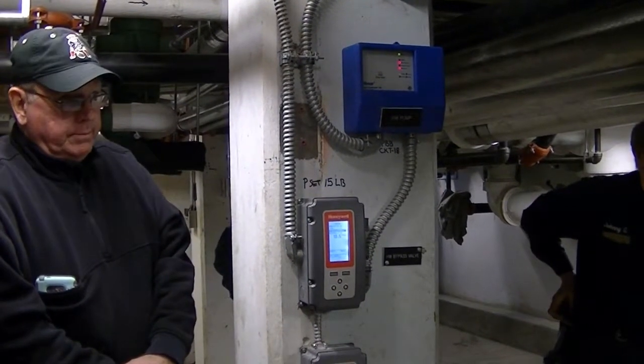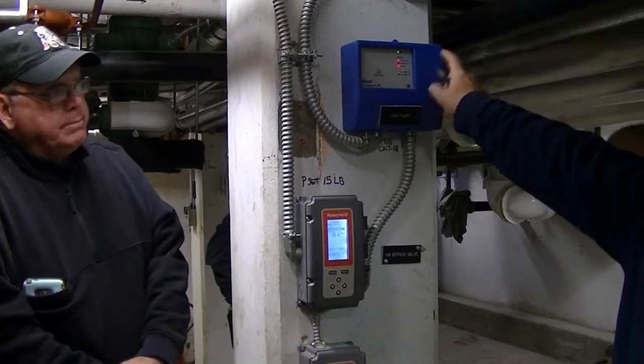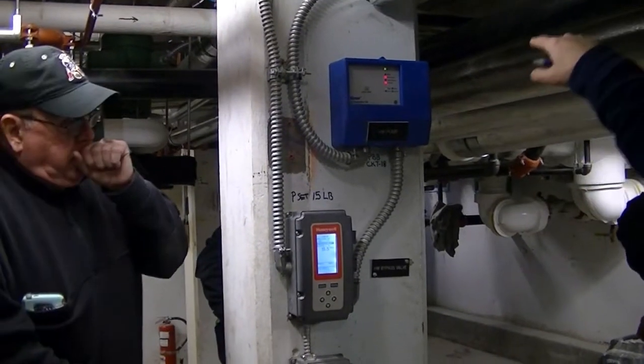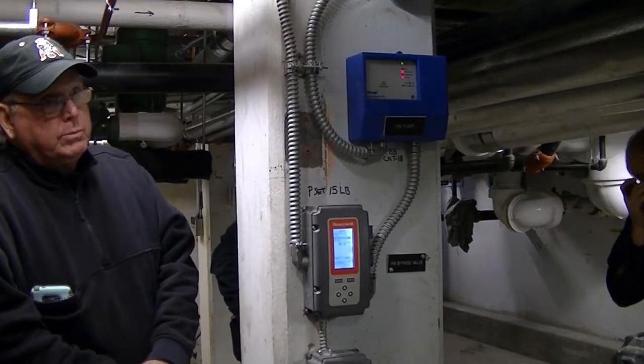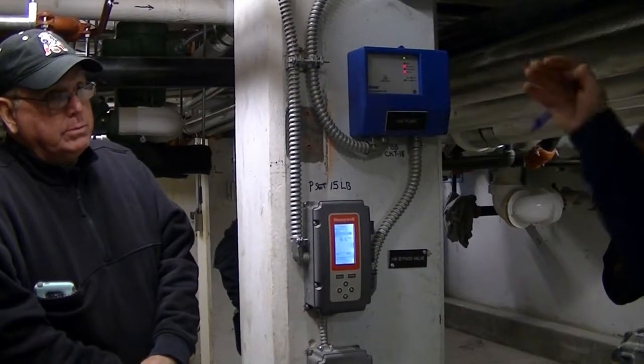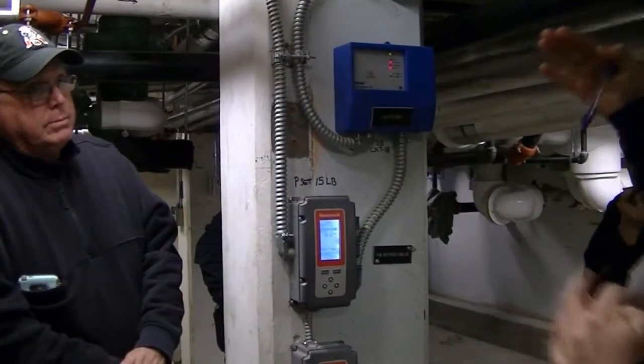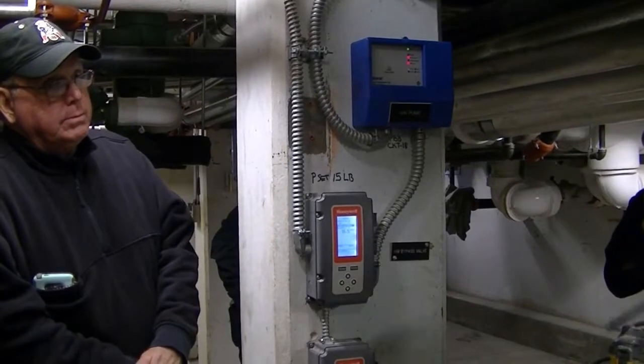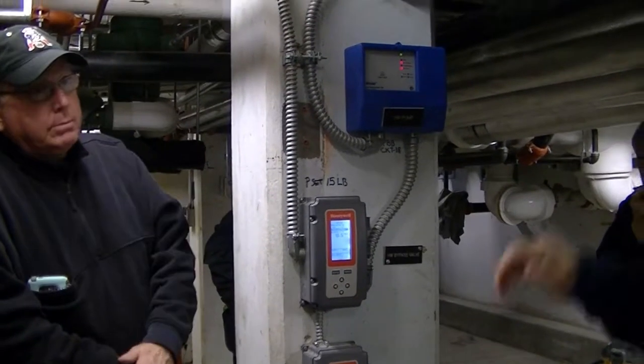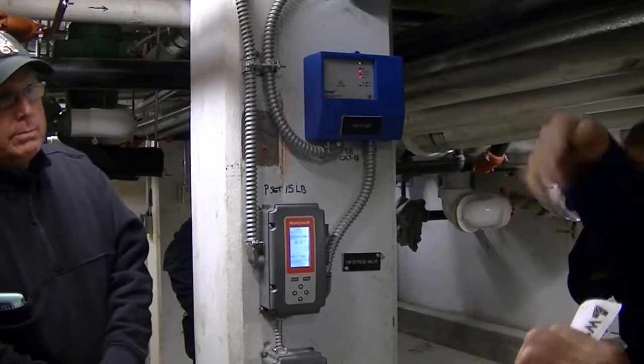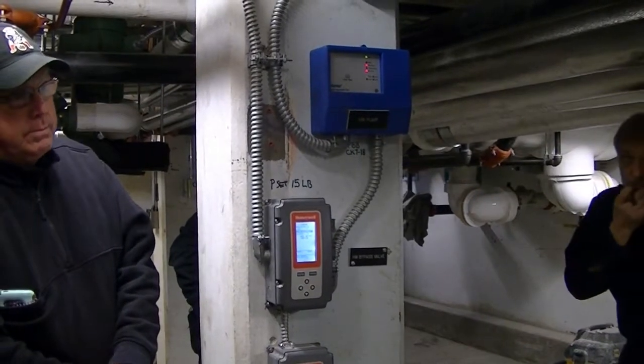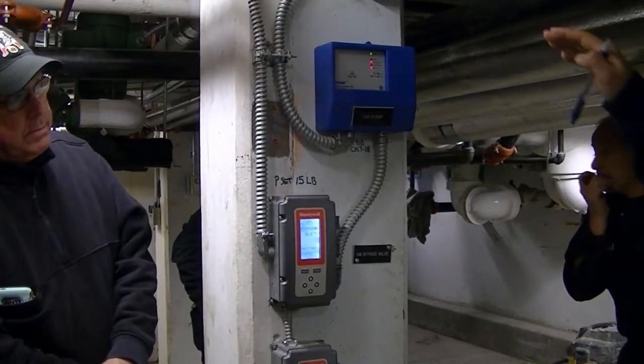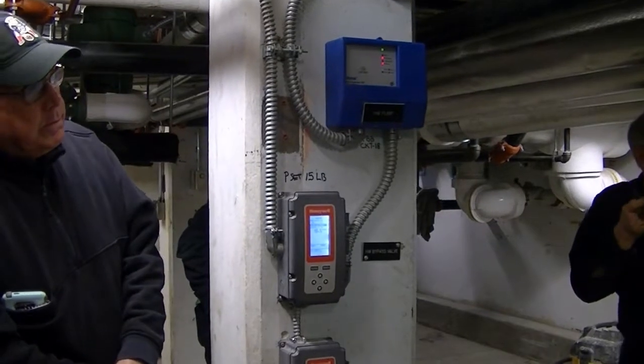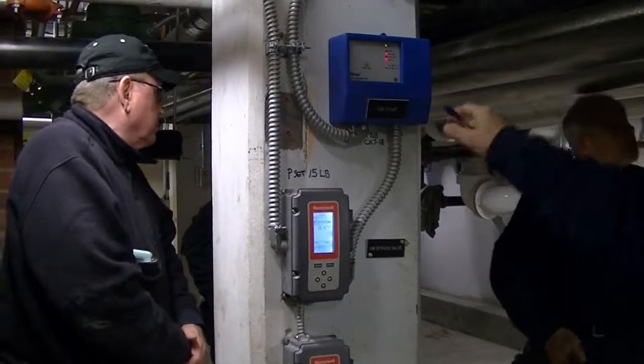No questions? Okay, so what this pump sequencer does is it receives an enable from the boiler, and it will start the pump. Now, wired to this is a flow switch, so as long as after 30 seconds or a minute that flow switch makes, everything's grand, okay? What type of flow switch is it? It's a paddle switch, okay? It's mounted, I believe, on one of these pipes here. I can point it out if you like.